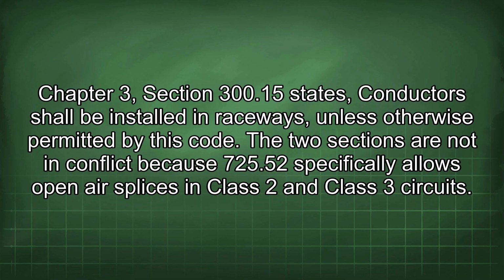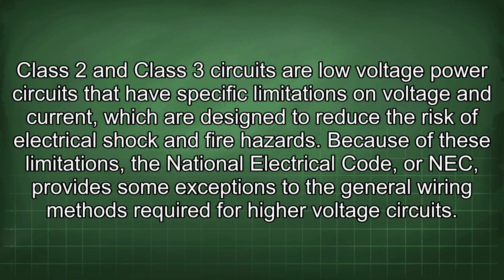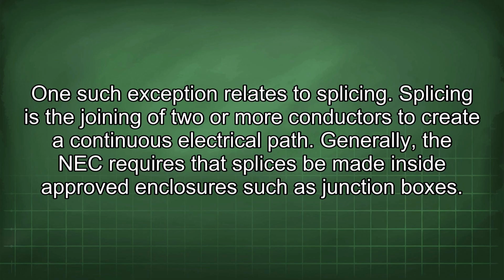The two sections are not in conflict because 725.52 specifically allows open-air splices in Class 2 and Class 3 circuits. Class 2 and Class 3 circuits are low-voltage power circuits that have specific limitations on voltage and current, which are designed to reduce the risk of electrical shock and fire hazards. Because of these limitations, the National Electrical Code, or NEC, provides some exceptions to the general wiring methods required for higher voltage circuits. One such exception relates to splicing.